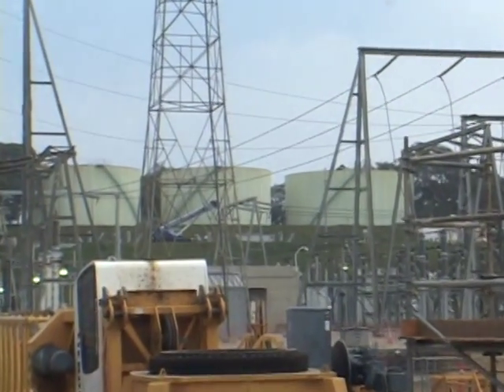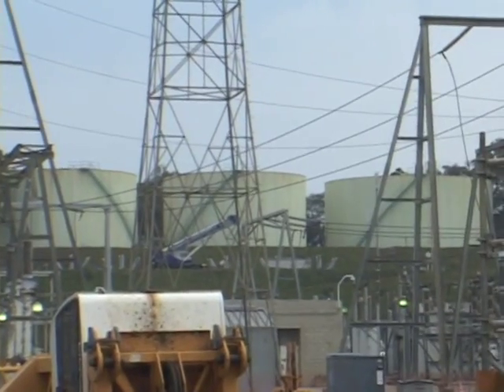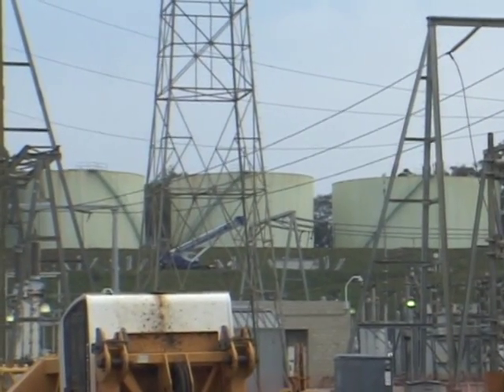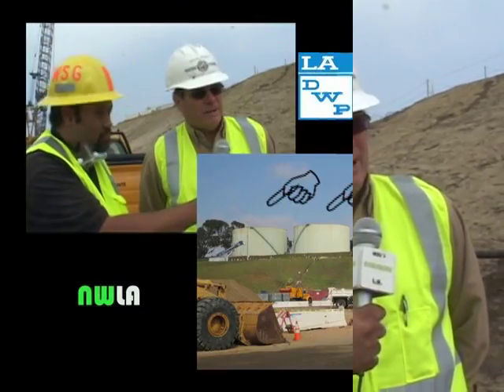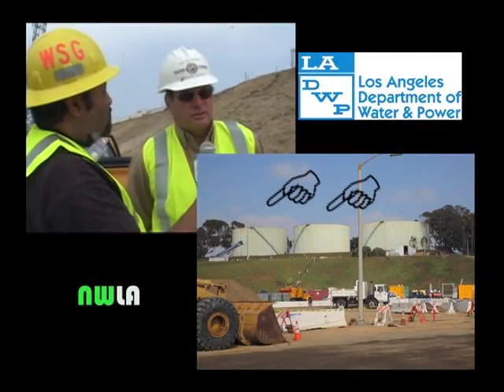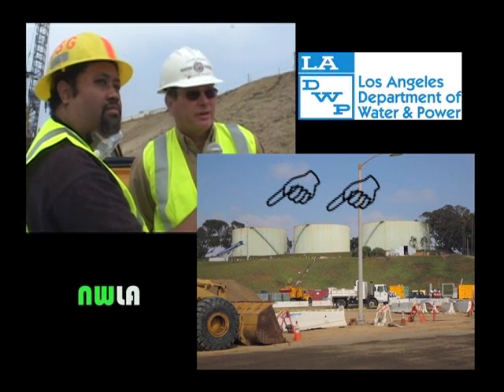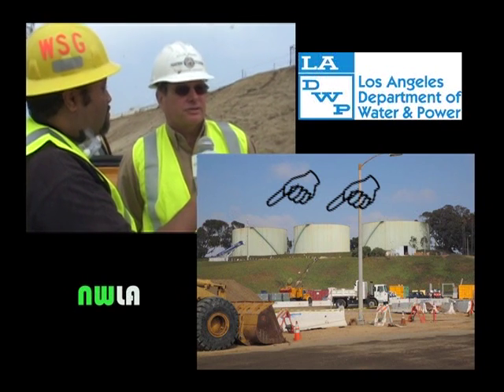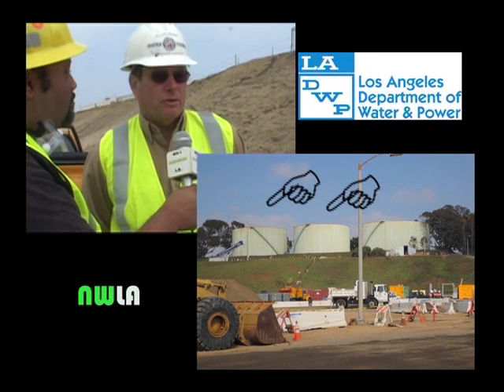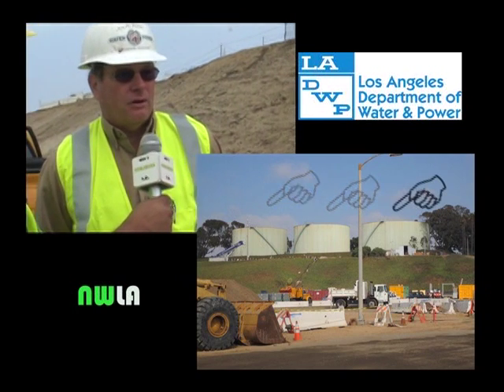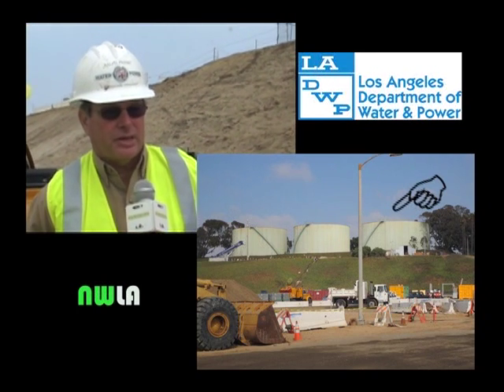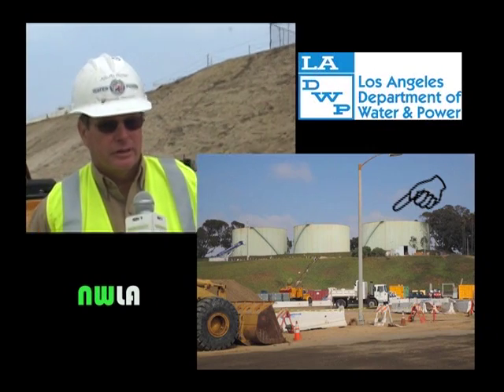You have two storage tanks filled with water that can keep this power plant going even if the city water supply is cut off for any reason. We have two service water tanks, about 1.5 million gallons each, giving us somewhere in the neighborhood of 30 days worth of water in case we have to do without water from the city. We also have a condensate tank about the same size for the pure water.